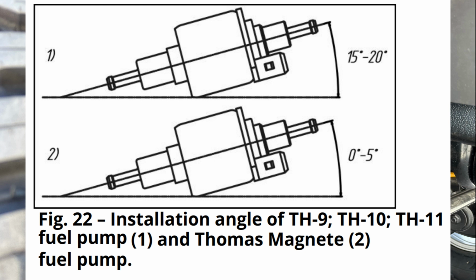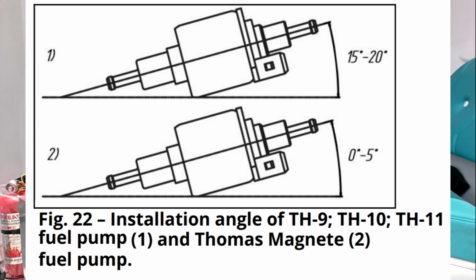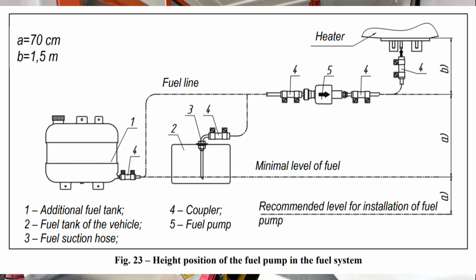in the fuel tank, but not lower than 70 centimeters of the minimal fuel level, see figure 23.a. But the distance between the fuel pump and the heater cannot be greater than 1.5 meters, see figure 23.b. The fuel pump should be positioned with a slight angle pointing upwards, see figure 22. If for some reason the fuel pump seal is compromised, it is advised to install the fuel pump lower than the heater to avoid leaks and flooding the heater with fuel due to gravity.